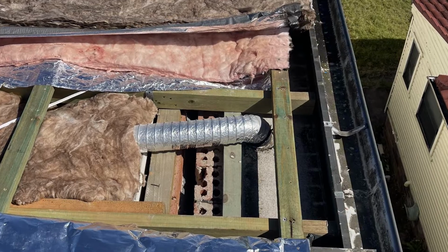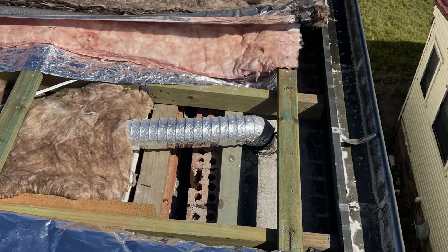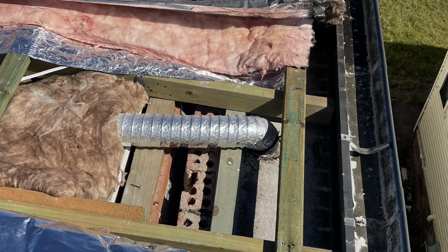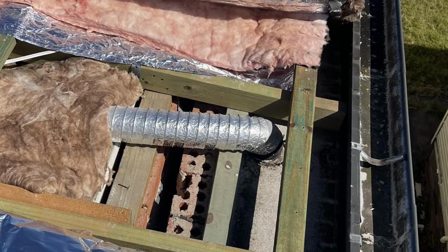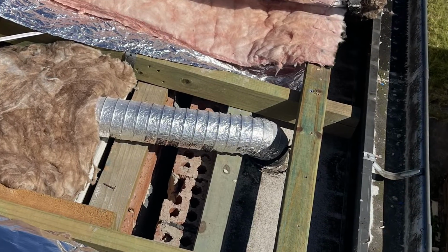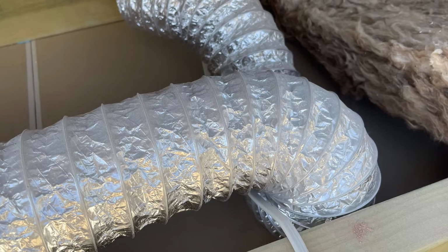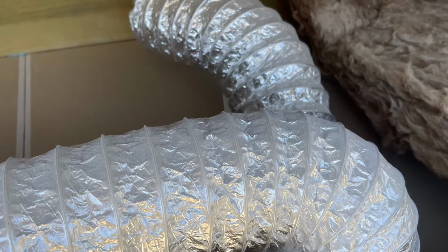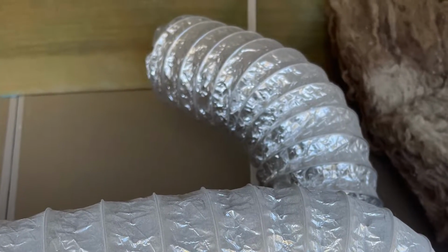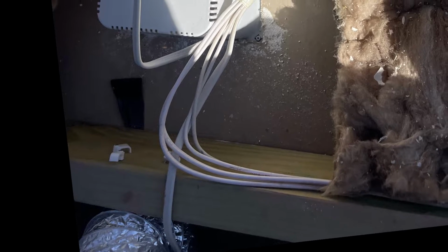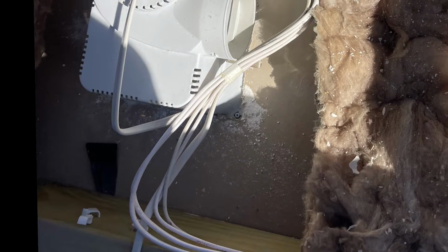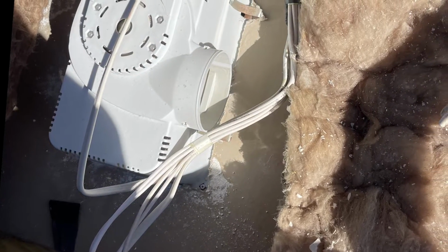Even quite new roofs, like this one for instance, there's provision for venting the bathroom out in under the eaves, if you can look at this picture. But when we took the roof off, we saw that the duct was not even connected to the exhaust fan. It was just lying loose, and obviously the person who put the exhaust duct in didn't think it was that important to actually connect the duct.